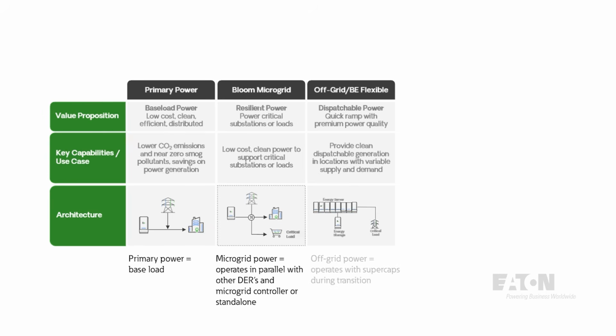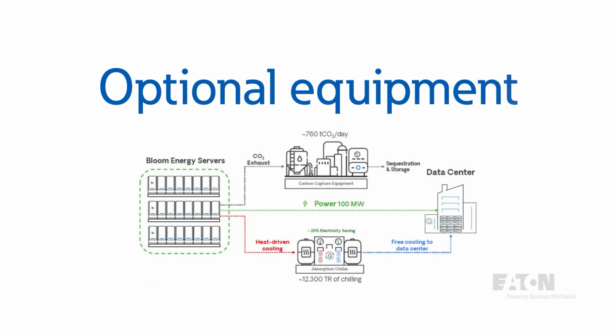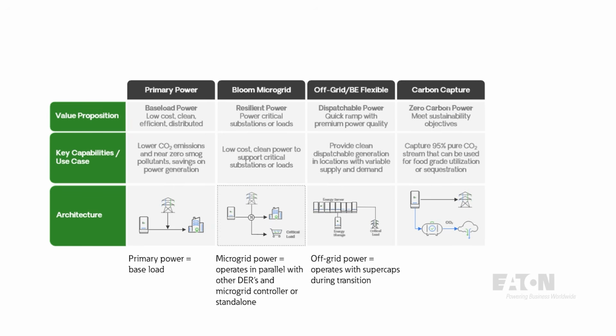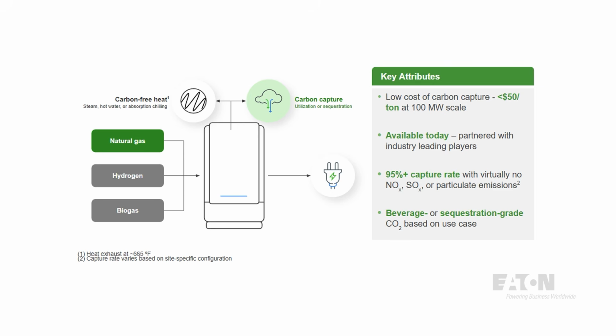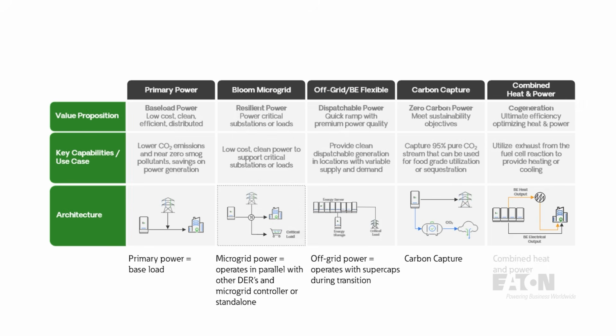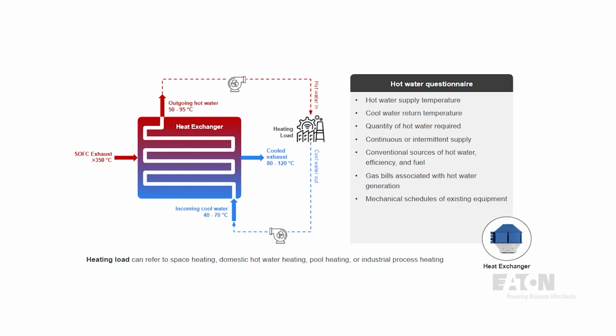It can also act as a UPS with loads fed downstream from the unit, with supercaps offering to buffer to protect against fast changes in load or full disruption of the utility power. As a grid-forming source, the fuel cell can run truly independent of the grid. In many cases, optional equipment can add additional benefits like carbon capture and combined heat and power. Carbon capture takes 95% of the pure carbon dioxide stream and captures it for use in food-grade or sequestration applications. For combined heat and power, the exhaust heat from the power modules is used to supplement existing heating and cooling equipment.